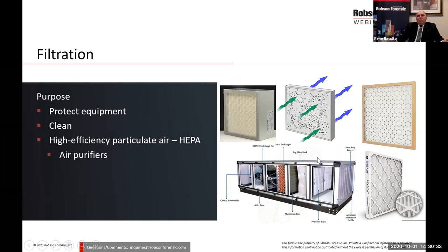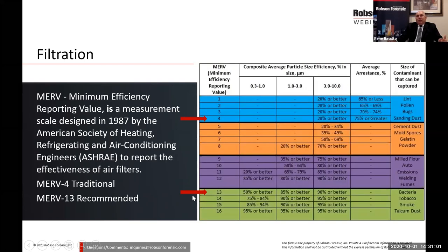But the more efficient the filters are, the more resistance you have to the air going across them. I mean, if you think about it, that's what the filters do. They prevent stuff from going through them. They're filtering out the air. So the more efficient, the more effective the filter is, the more resistance you have to the airflow. And that's something that needs to be taken into account when we're looking at modifying our systems and increasing the filtration. Not every piece of equipment can handle it.